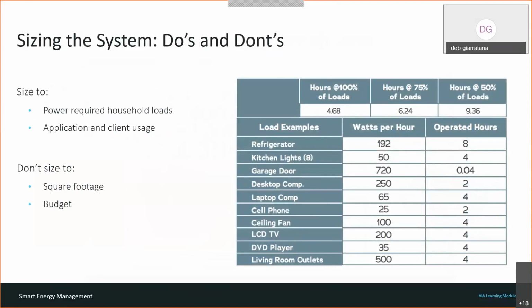You can see that where it says load examples, you have refrigerator, kitchen lights, garage door, all the way down to outlets and things like that. A simple look at a spec sheet for those items shows you the watts per hour that it uses. You figure out the loads and size the system to support those loads. We would not, for example, determine the size of a system based on somebody's budget, and we would not buy this or determine it by the square footage of a house. You have to use the information about the loads that they want to protect and that they want to use their battery for. That's the only way to determine size.